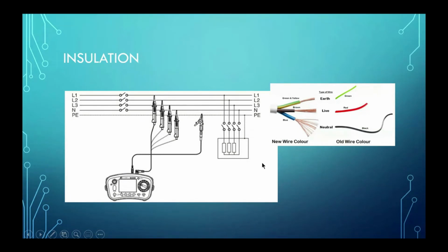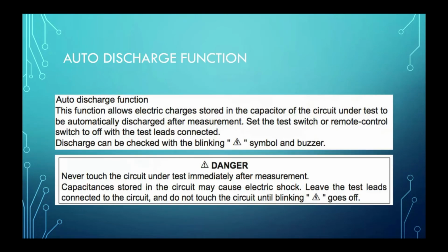Then another thing, you see here is your appliance or your equipment. For the insulation test, we need 500 volt DC or 1000 volt DC to test the insulator. This 500 volt or 1000 volt DC goes out from the instrument to test the electric circuit under test. It may spoil your appliance or your equipment, so please cut off this equipment before you run the test. Understand? Another thing is, an insulator is not a good conductor. Normally the resistance is very high, in mega ohm, so later you will see the test results are all in mega ohm. Understand? So I move to another function.